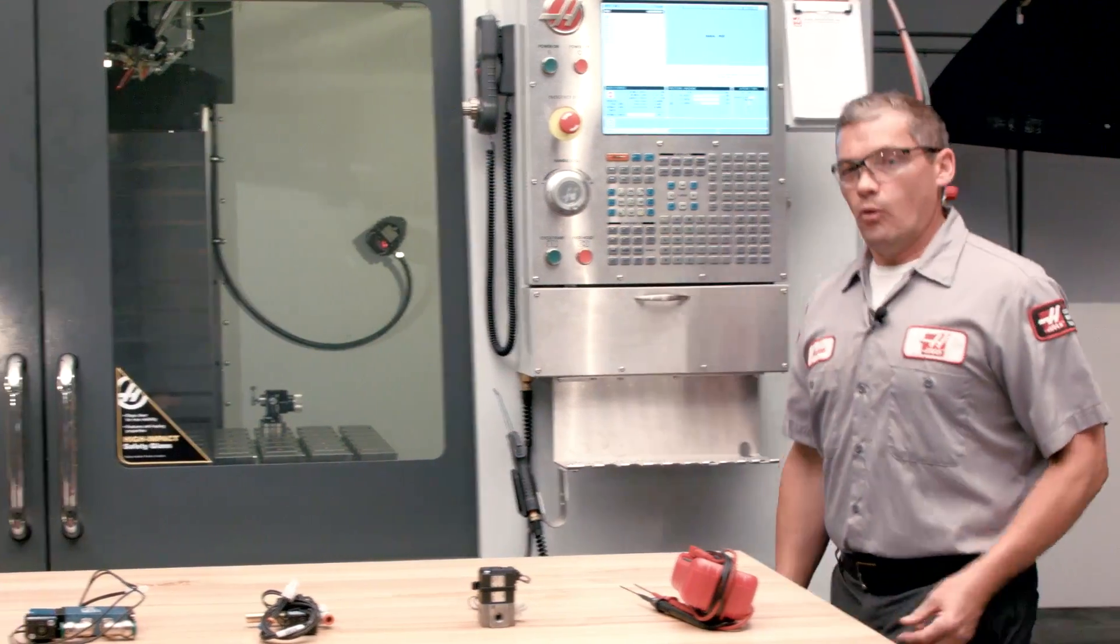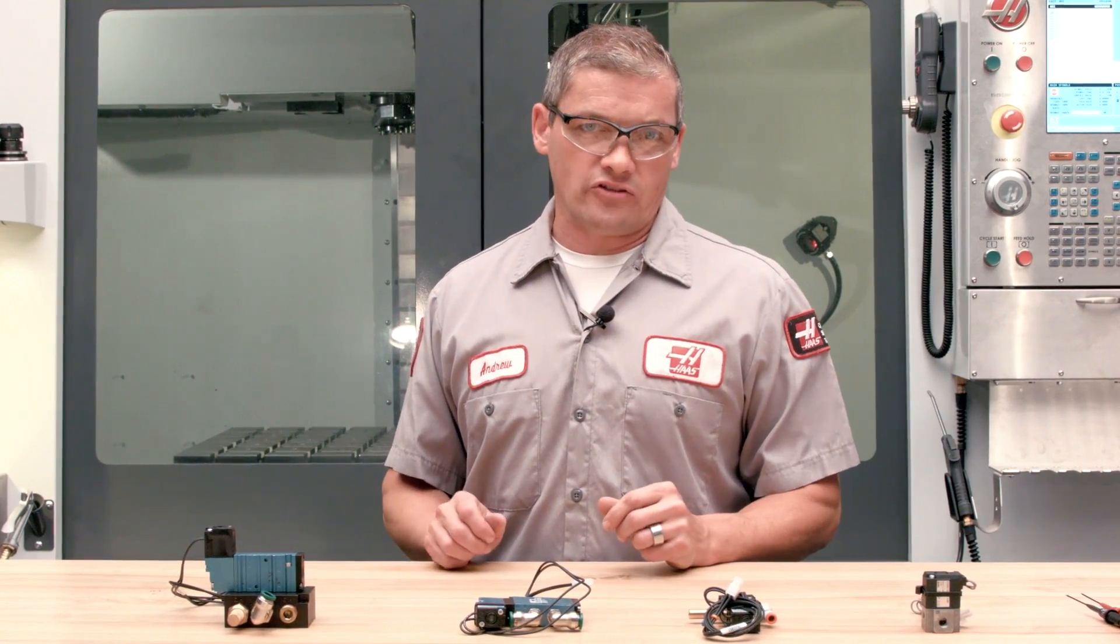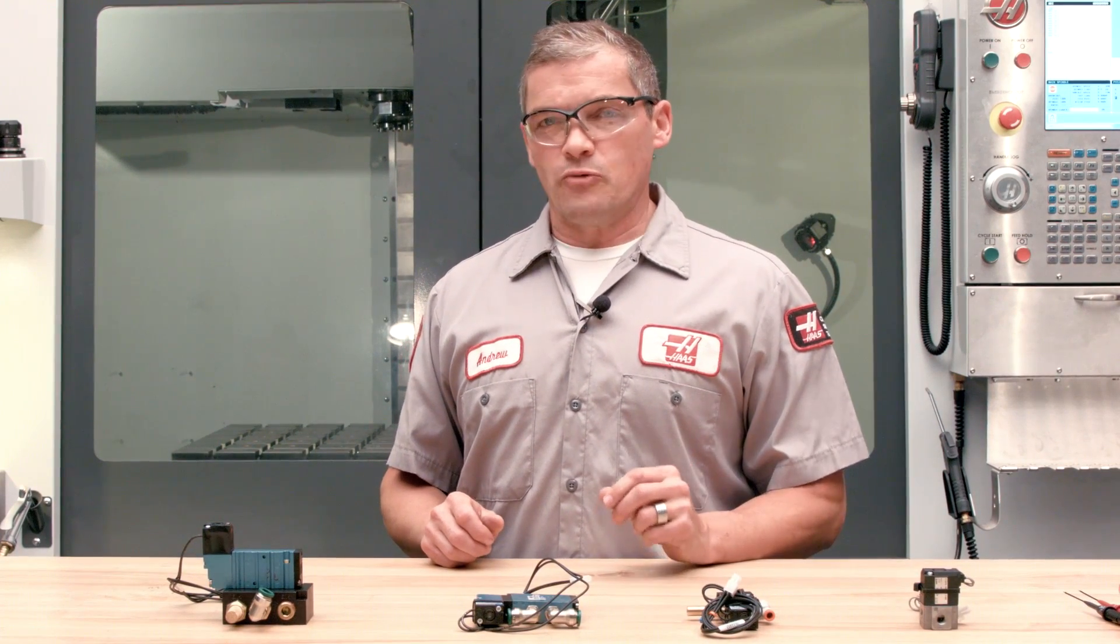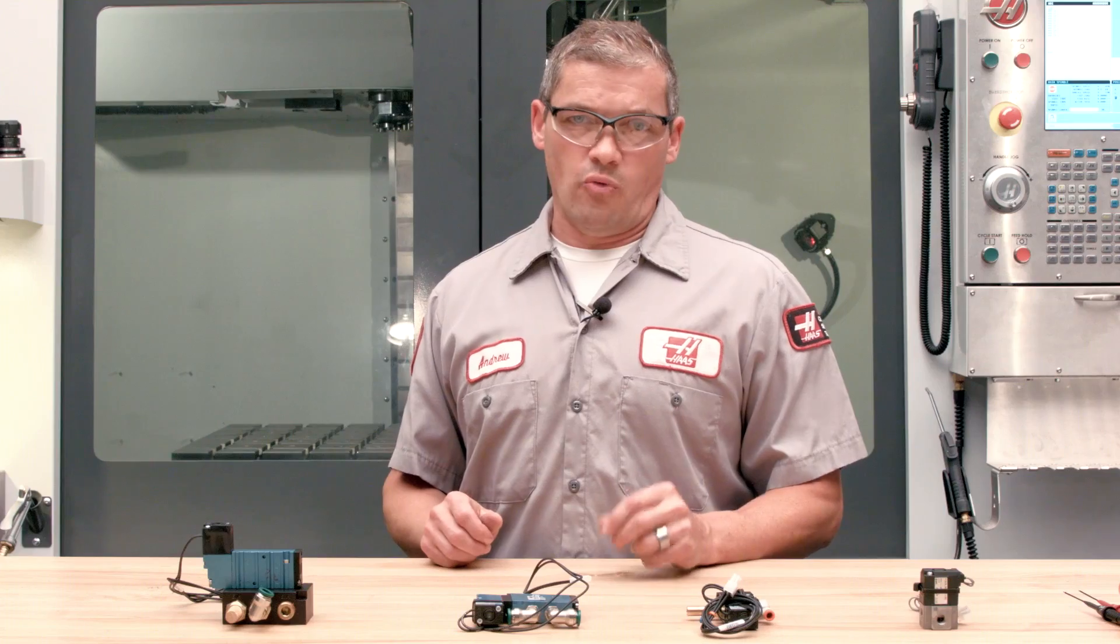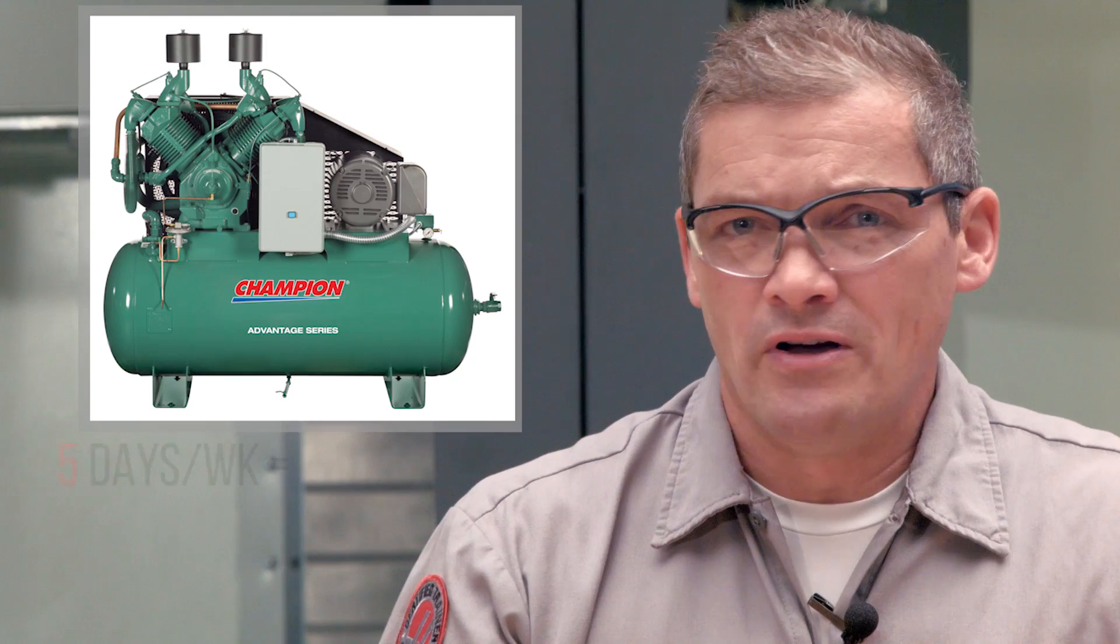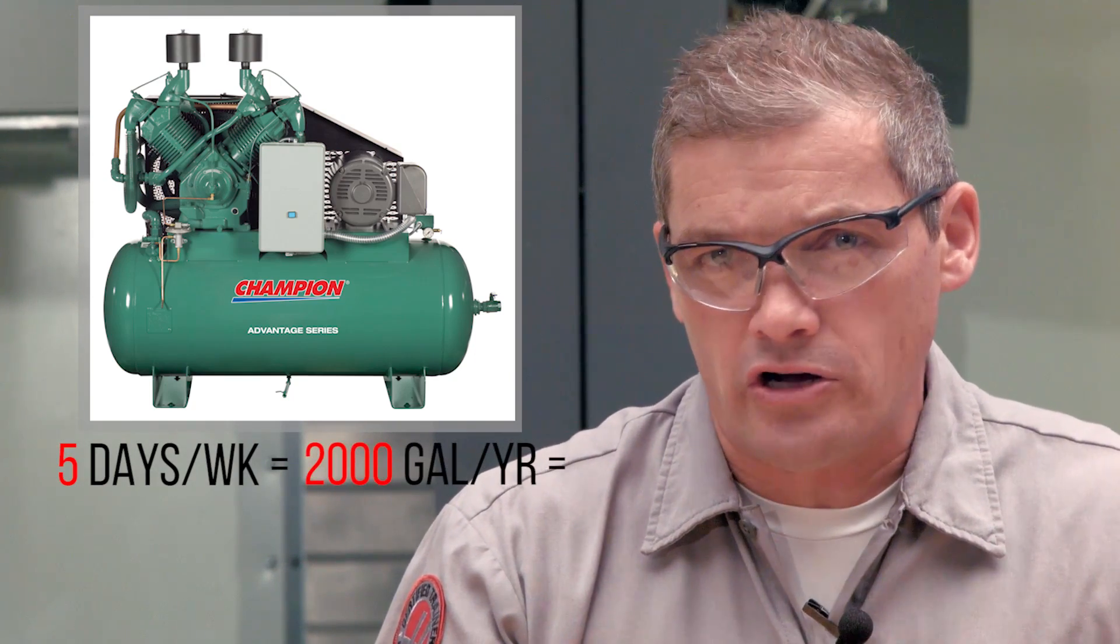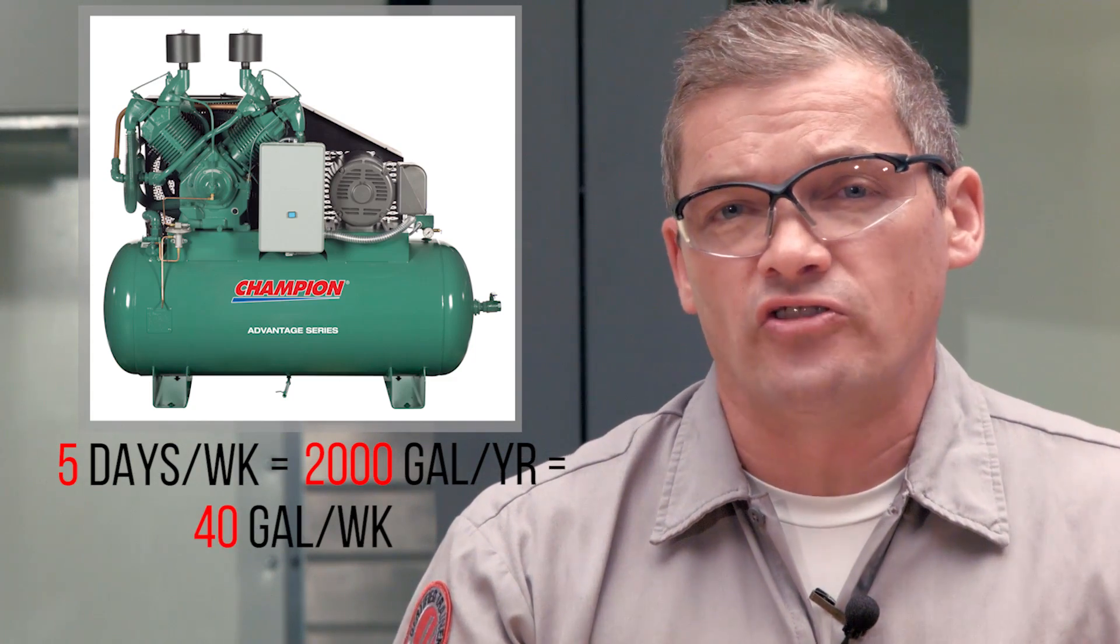You might ask yourself, why is it that so many compressed air installations seem to have problems with water in the airlines? The fact is that every compressed air system has the potential to have big problems with water. It turns out that your air compressor isn't just good at compressing lots of air. It's also pretty good at extracting lots of water as it's compressing that air. Consider this: a relatively small 100 CFM compressed air system running in a typical shop five days a week can easily generate over 2,000 gallons of water in a year. That's about 40 gallons going to the receivers and airlines all throughout the shop every week.